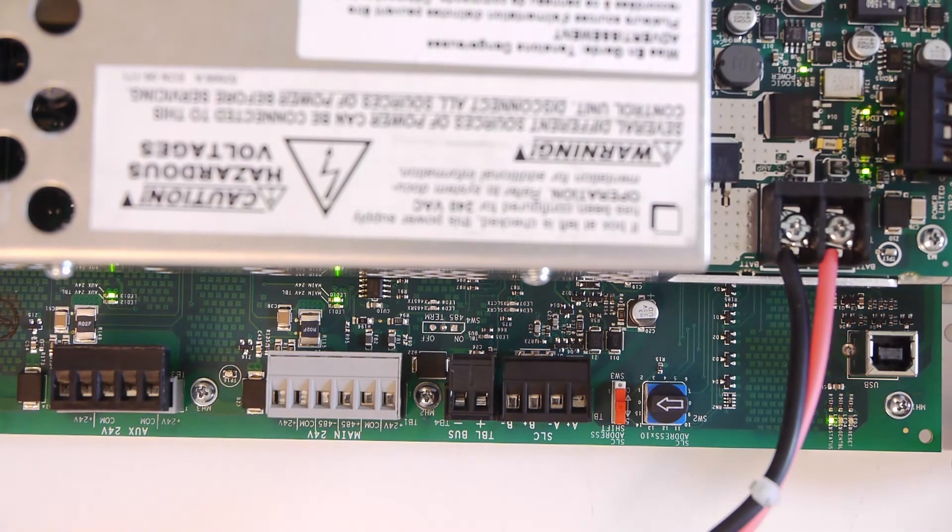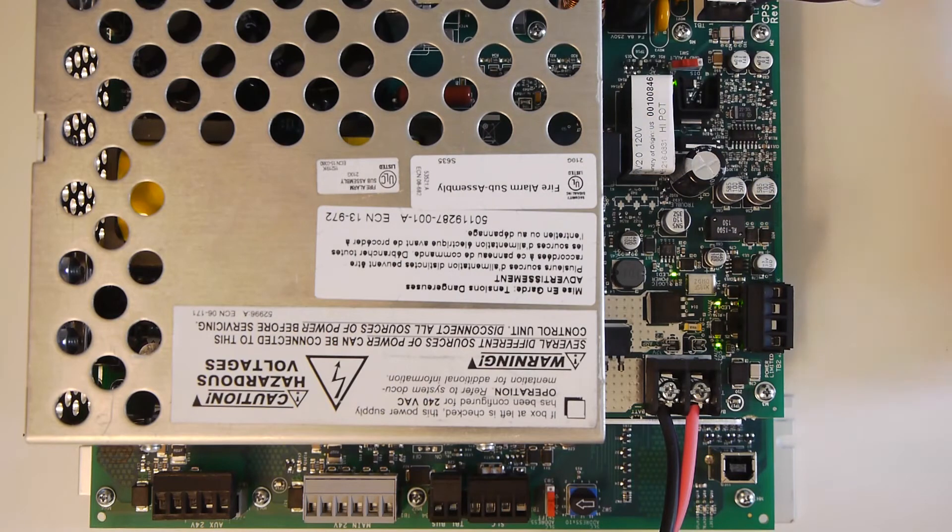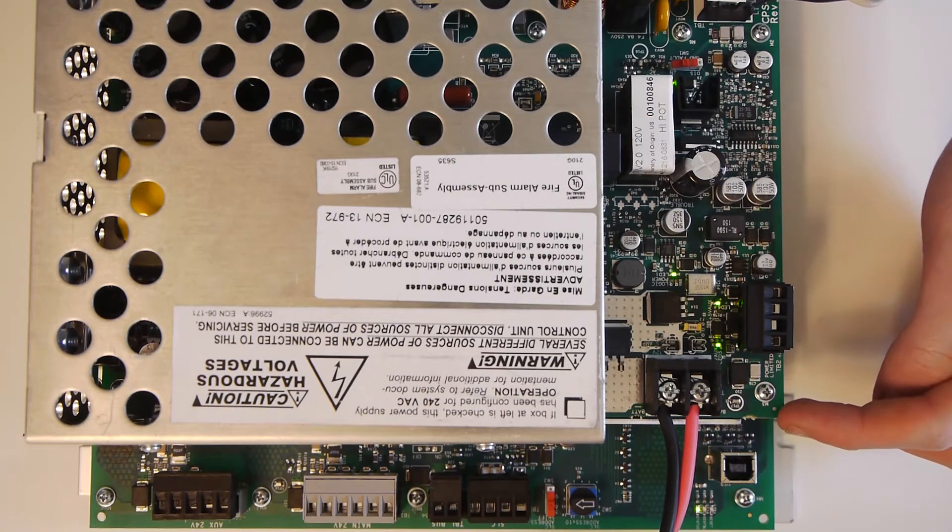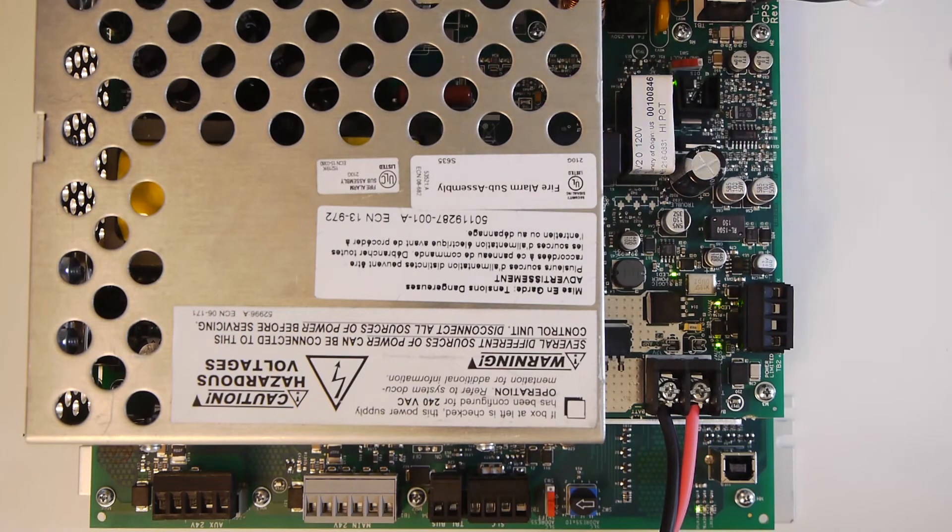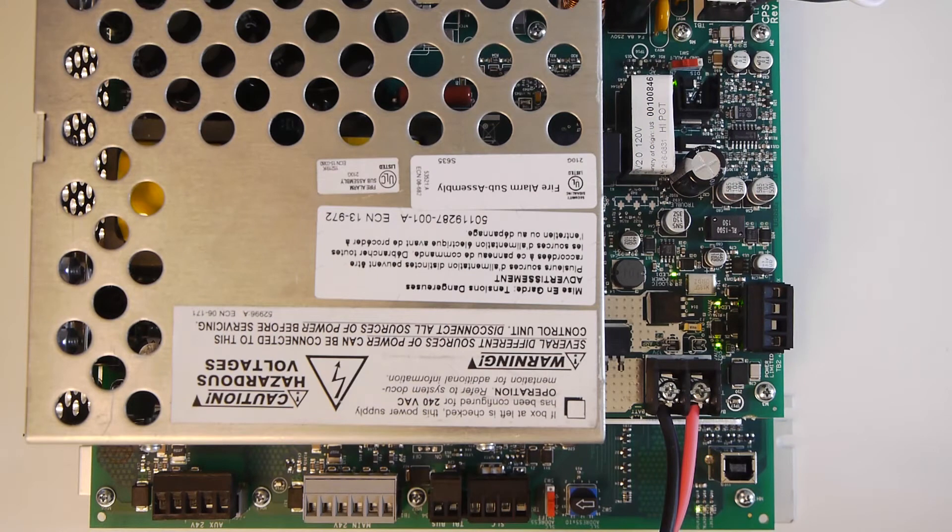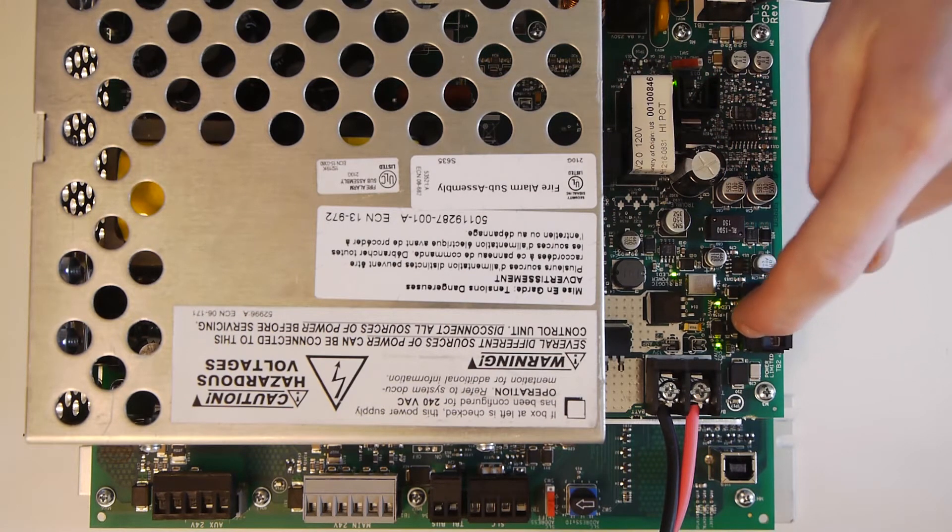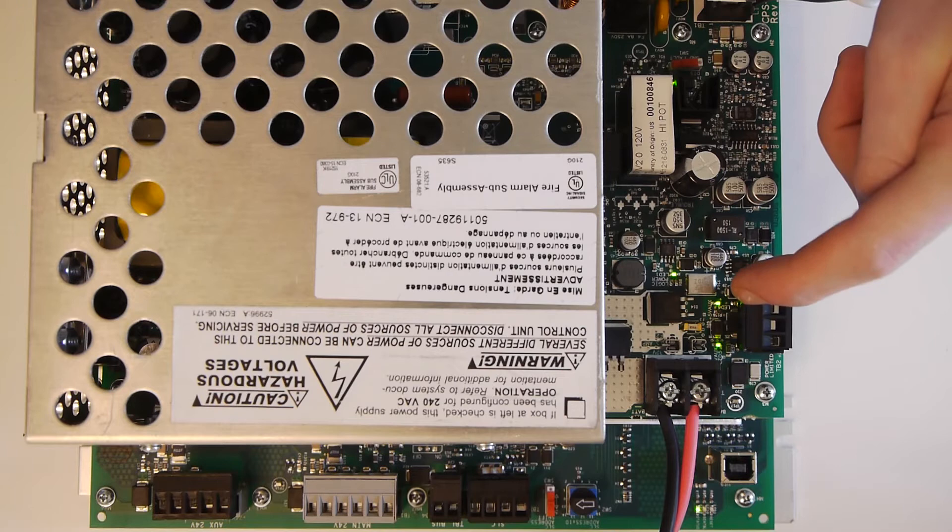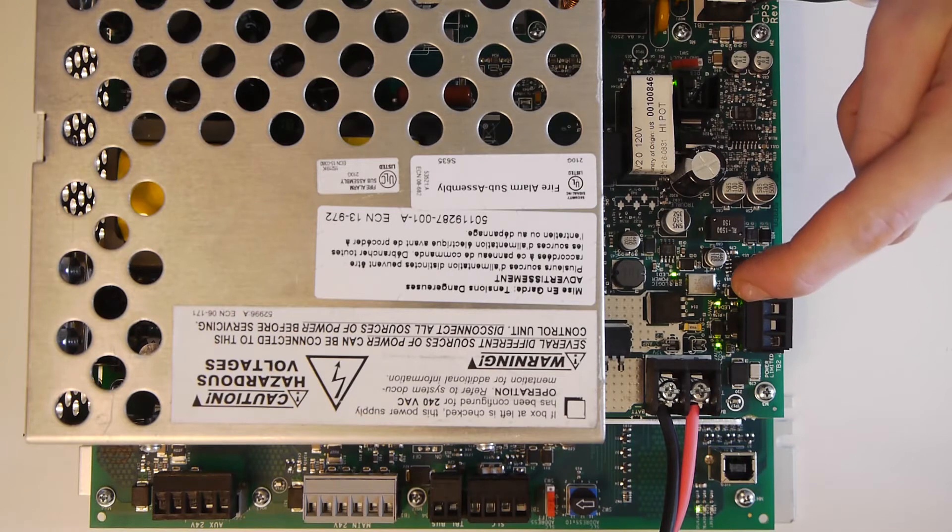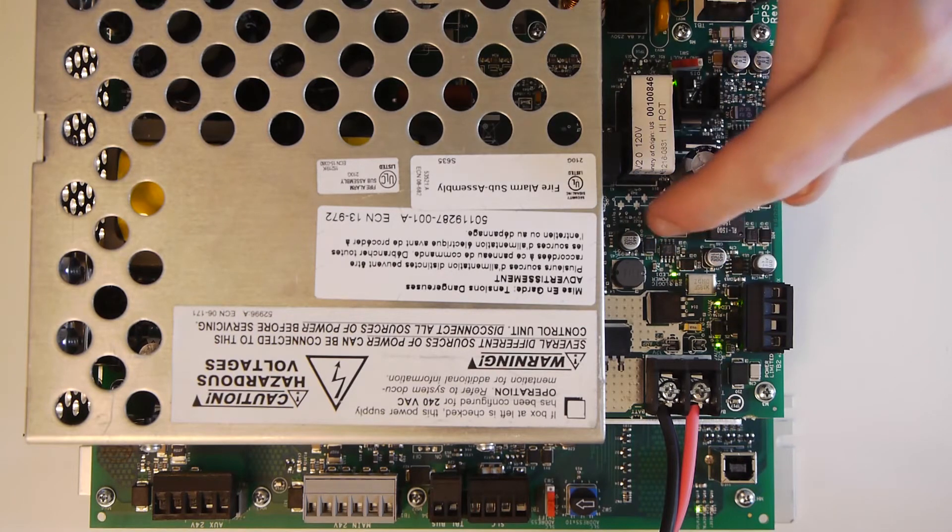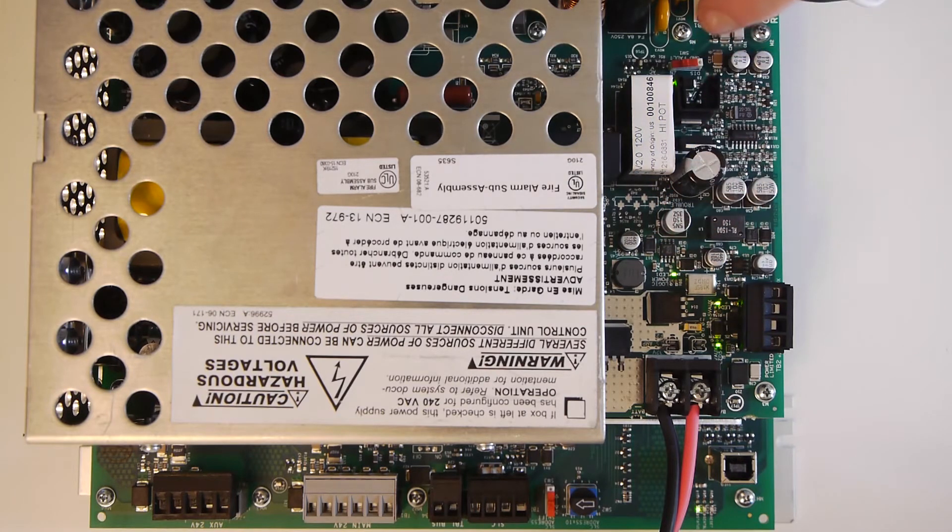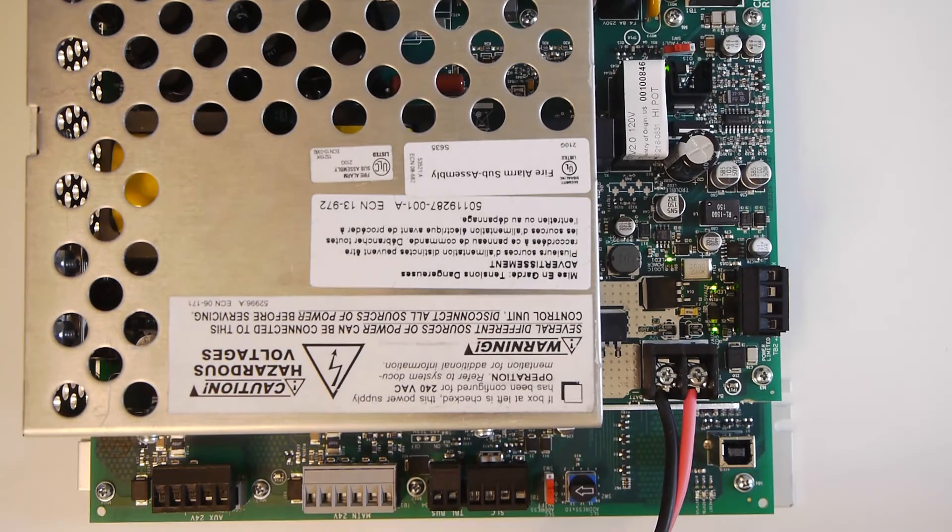So now let's go over the lights. First of all, on the CPS 24 board, which is this one, normally there are four green lights on when the power supply is in normal mode. There's a green light for the 24-volt rail. There's one below it for the 5-volt rail. Right here there's a logic power light. And right here there's an AC power light.